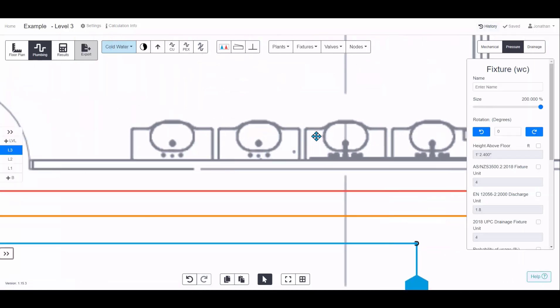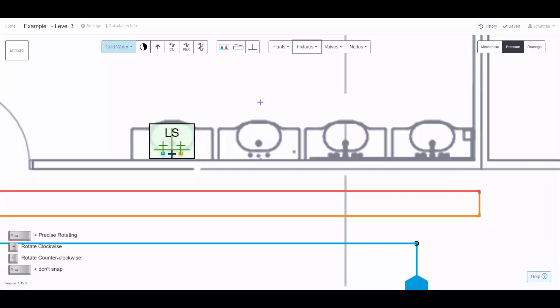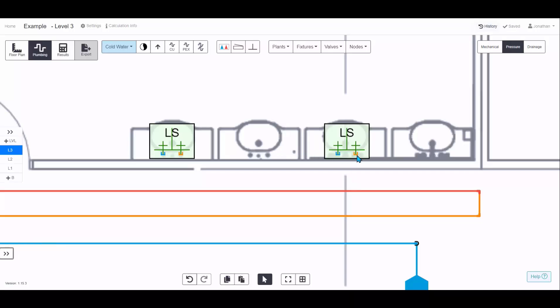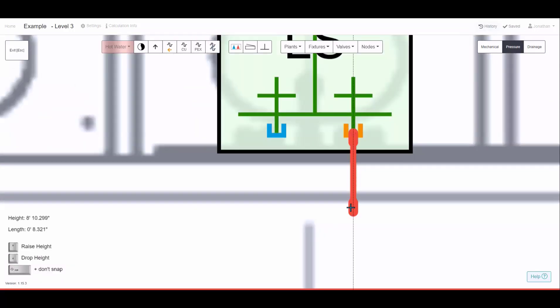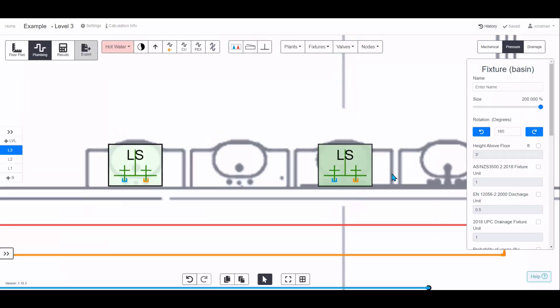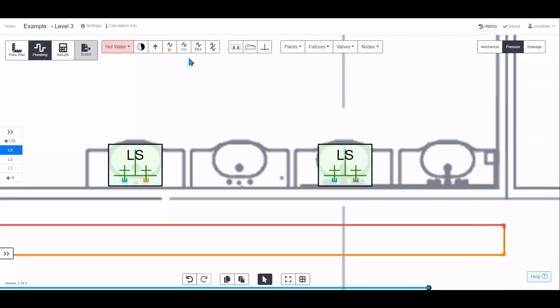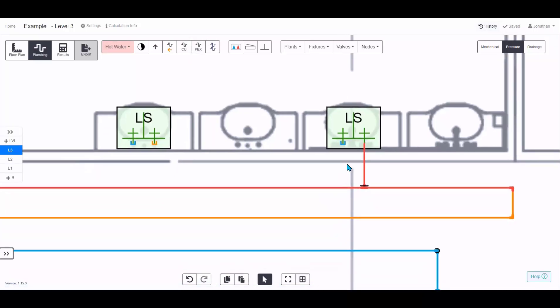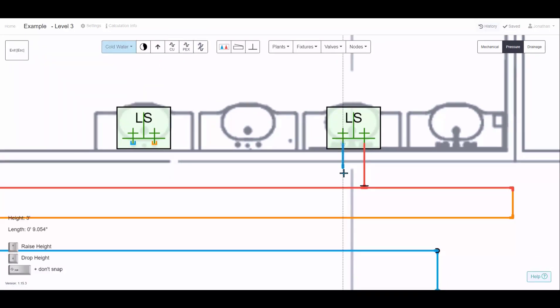Connecting two fixtures such as basins or lavatory sinks, where they have a warm water connection, is a little bit more difficult. So look at two examples here. Because it requires warm water, it doesn't let you connect hot straight to it. As we can see here, as we hover over this, that cap doesn't disappear. If we want to change that, in the fixtures properties, allow the systems to connect for warm water. It'll turn that cap from orange to gray, and now as we try and connect hot water, hover over it once again, you can see that cap disappears. And now we'll connect the cold water up, just like that.